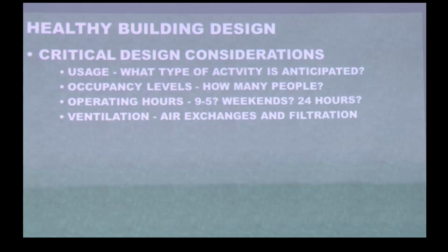The ventilation, air exchanges, and filtration. How many people are going to be in your building? Is it going to widely fluctuate? So here's a fine example. In this space, I might use it for a training room for 10 people, or we may have 80 people as we have today. Your system has to be able to accommodate that without penalizing you on days when you do have 10 people. That's when your CO2 sensor comes in handy. You can allow more air into your system or back it off, and you have a minimum amount of air to deal with the 10 people in training room scenario.